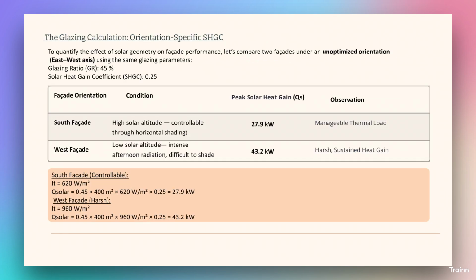The glazing calculation: orientation-specific SHGC. To quantify the effect of solar geometry on facade performance, let's compare two facades under an unoptimized orientation, east-west axis, using the same glazing parameters. Glazing ratio, GR, 45%. Solar heat gain coefficient, SHGC, 0.25. Columns: facade orientation, condition, peak solar heat gain Qs, observation.